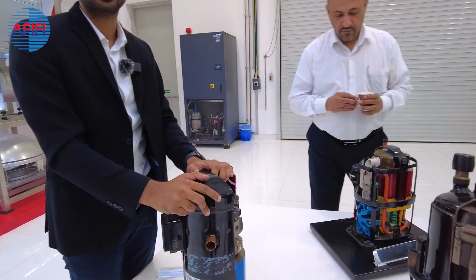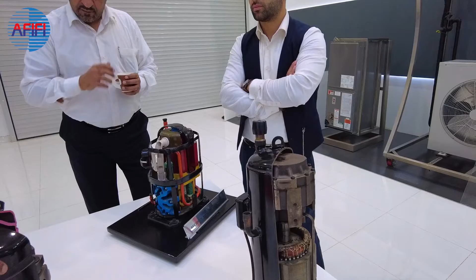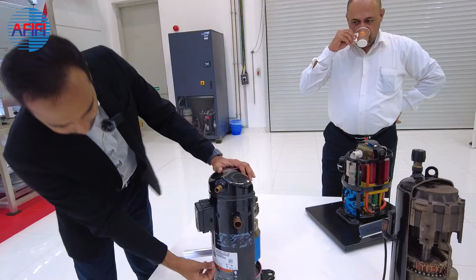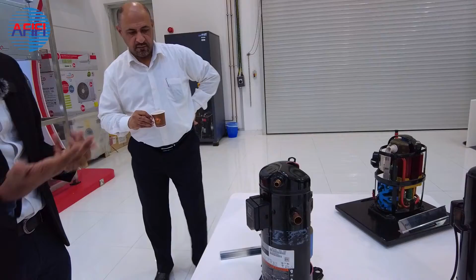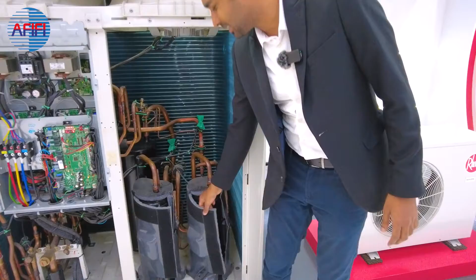This is the ordinary reciprocating compressor, the single piston reciprocating compressor. We used to use that in like 2015, 2016, but we don't use it anymore. The VRF inverter compressor is exactly the same, the only difference being that it has variable frequency, so the speed goes up and down. The rotations per second changes to control the flow. For example, this one is locked at 1750 RPM. Either you have 0 or 1750, that's it. But with the inverter, the rotations per second just changes. That's exactly where this oil return is nice, since a lot of oil goes through this. It's the same compressor that we see here. It's got an acoustic liner for sound insulation. Is a scroll quiet by nature? Yes, it's quiet by nature.